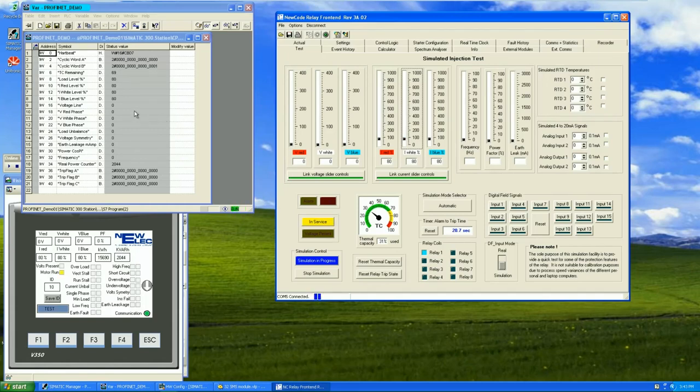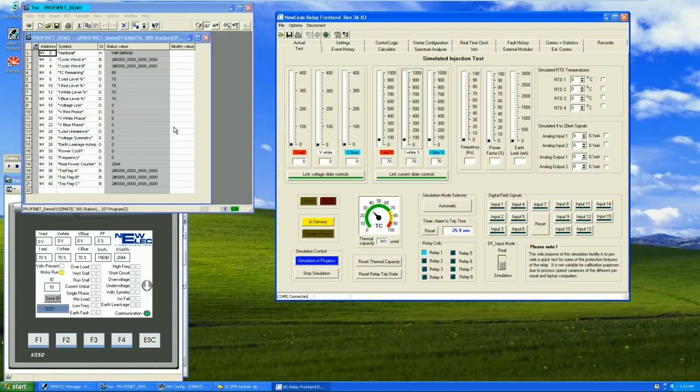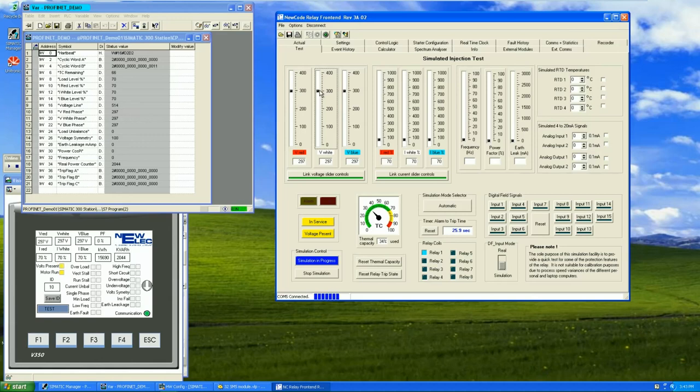If we take it to overcurrent, you will see that the overcurrent LEDs and the any alarm flag bits also go high. So this unit is currently reacting as if it's currently got a drive on. The same as when we add voltage, you will see that the voltage present flag and all the load voltages will show. Also note that this is also directly showing on the Modbus currently as well.